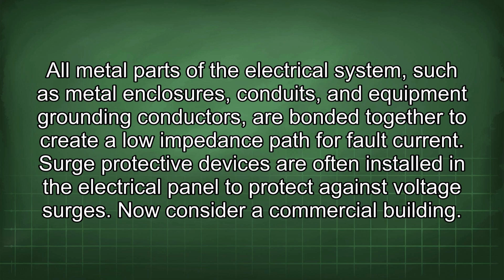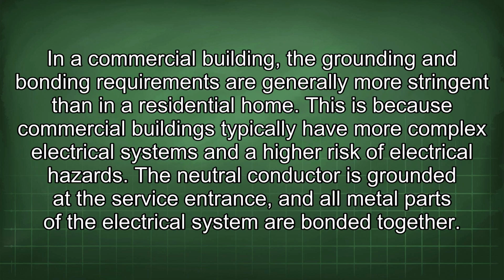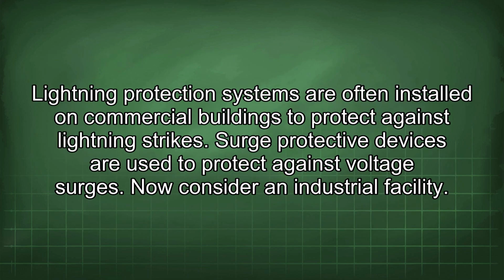Now consider a commercial building. In a commercial building, the grounding and bonding requirements are generally more stringent than in a residential home. This is because commercial buildings typically have more complex electrical systems and a higher risk of electrical hazards. The neutral conductor is grounded at the service entrance, and all metal parts of the electrical system are bonded together. Lightning protection systems are often installed on commercial buildings to protect against lightning strikes. Surge protective devices are used to protect against voltage surges.